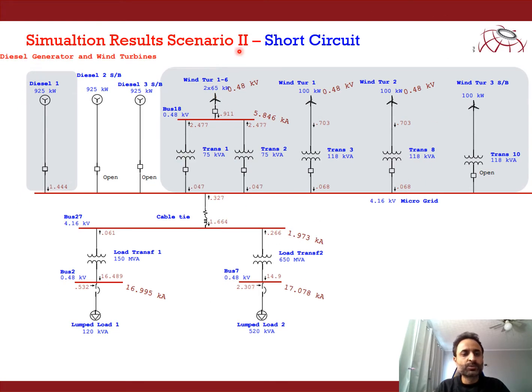In the same scenario, with the diesel generator and wind turbine, if we talk about short circuit current, now in addition to diesel generators we also have wind turbines, which will pump short circuit current into the buses in case a short circuit happens. So the total fault current has now increased to 1.973 kiloampere. On the secondary side, at the load end, this is around 17 kiloampere, which is less than 25 kiloampere. So this result is also within limits.